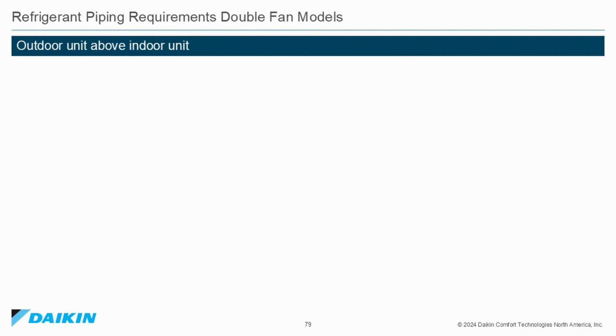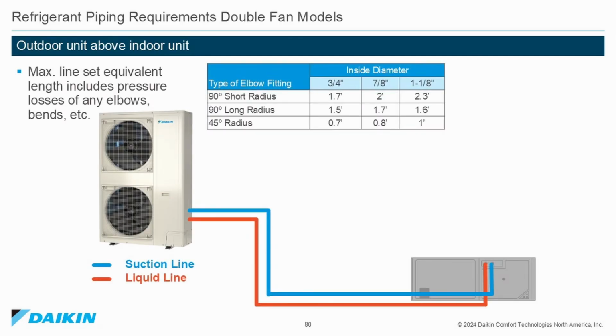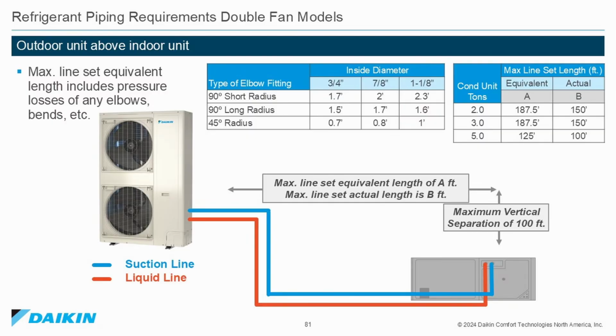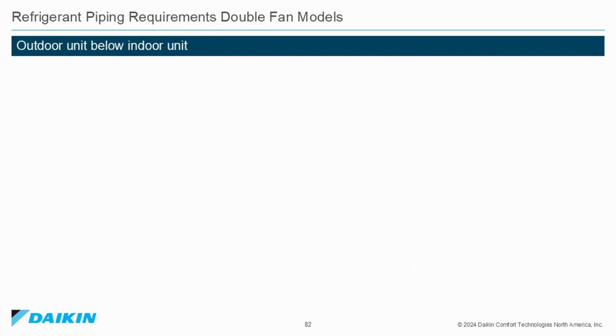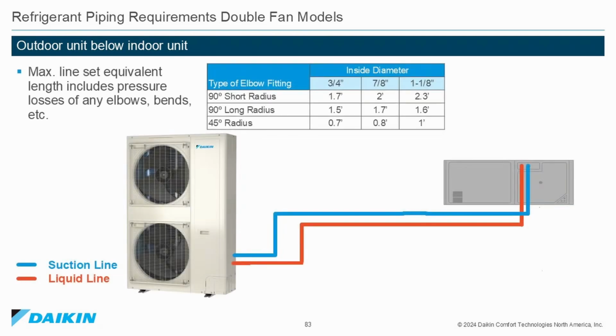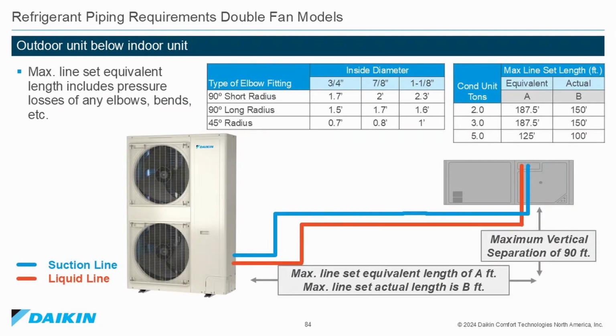Refrigerant piping requirements for the double fan models. When the outdoor unit is above the indoor unit, maximum line set equivalent length includes pressure losses with any elbows, bends, etc. On the double fan model, you'll see that the maximum equivalent length is, on the 3-ton for instance, 187.5 feet, with 150 feet actual line set length, with a maximum vertical separation of 100 feet. If the outdoor unit is mounted below the indoor unit, again for the 3-ton, maximum equivalent length is still 187.5 feet, maximum vertical separation 90 feet, actual line length 150 feet.